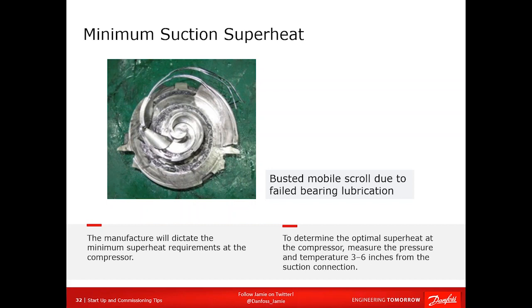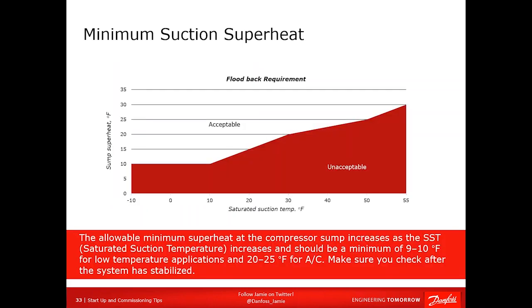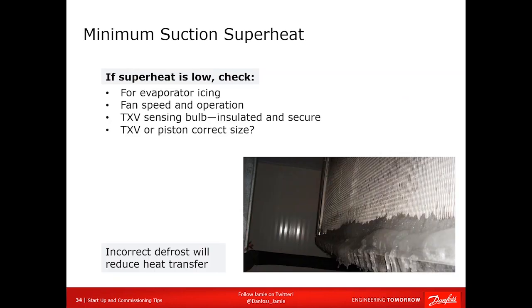All right. So believe it or not, yes, scrolls can take a bit of liquid. However, that top bearing, the one that gets burned out under the middle of the scroll underneath, is also the one that gets dry cleaned when you have refrigerant coming back into the oil. And as soon as you lose lubrication, it seizes, it's game over. All right. So measure your saturated suction superheat 5 inches away from the compressor. Look at here. You've got maybe 20 degrees of superheat required, 25 degrees of saturated suction superheat on air conditioning, down to 10 for freezers. All right, make sure you stay within that range.